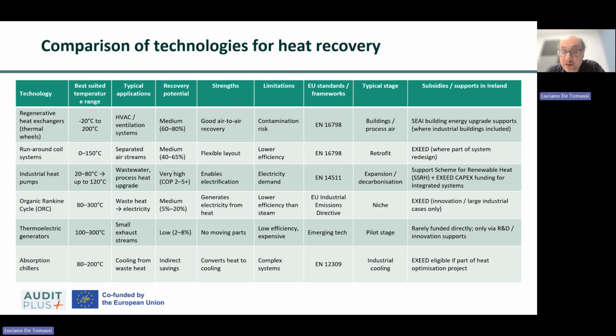The heat-absorbing matrix is mounted as a large circular wheel and is slowly rotated by a small electric motor and drive system, typically at a speed of around 5 to 20 revolutions per minute, so that sections of the matrix alternately pass through the exhaust and supply air streams to transfer heat continuously. They are common in offices, hospitals, educational facilities, data centers, and industrial buildings. Heat recovery efficiencies typically range from 60 to 90%.